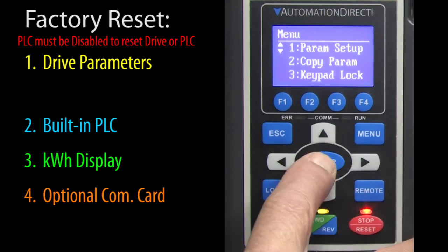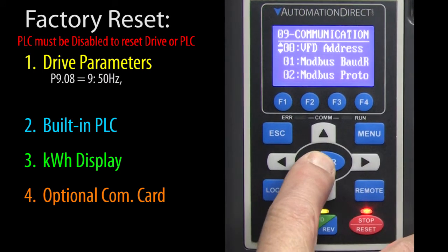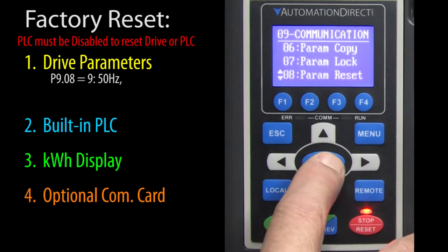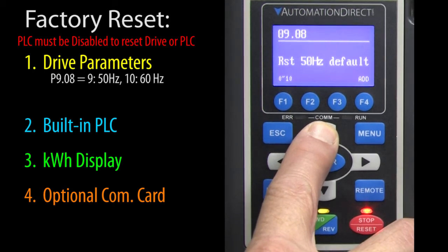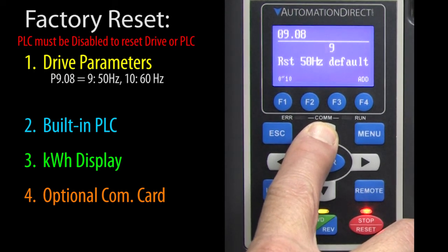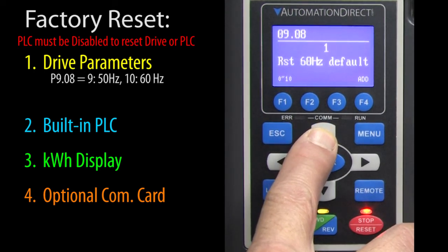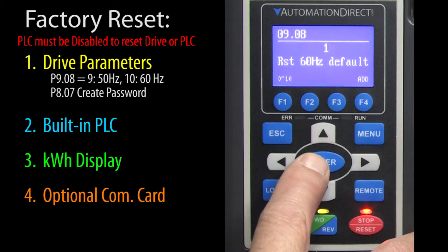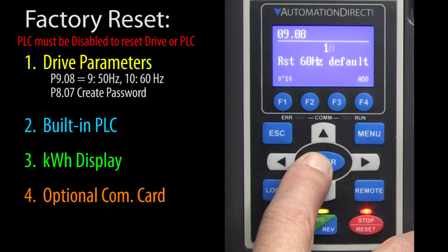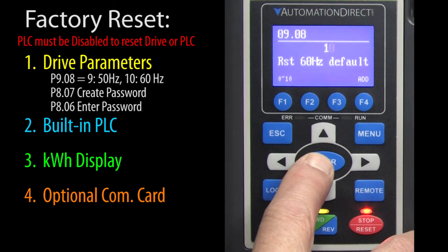To reset the drive, go to parameter 908 and enter a 9 to reset to 50Hz or a 10 to reset to 60Hz. A word of caution: if you created a password in parameter 807, you'll have to enter it in parameter 806 to be able to reset the drive's parameters.